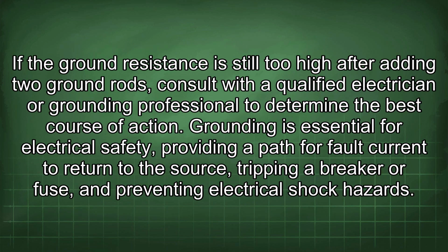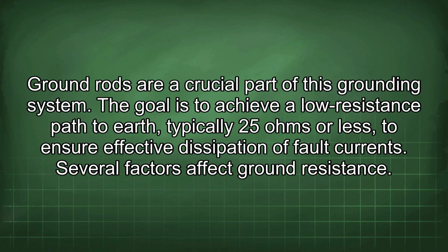If the ground resistance is still too high after adding 2 ground rods, consult with a qualified electrician or grounding professional to determine the best course of action. Grounding is essential for electrical safety, providing a path for fault current to return to the source, tripping a breaker or fuse, and preventing electrical shock hazards. Ground rods are a crucial part of this grounding system.